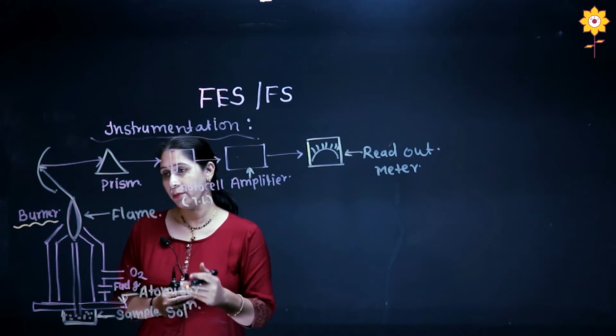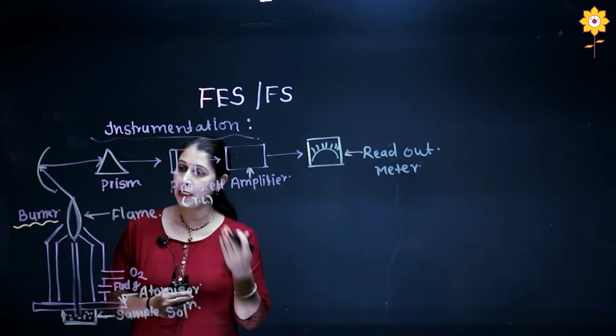So what exactly is meant by the total consumption burner? In this burner whatever sample is drawn is completely utilized for atomization. That's why we call it a total consumption burner. Now you can see in the diagram. The diagrammatic representation shows the burner is used for getting a flame. Okay, so a high thermal energy flame is needed for the atomization process, so we are using it here. O2 gas is used as an oxidant along with the fuel gas, which is used for production of a high energy flame. And the sample is drawn from the sample port into the atomizer unit by suction.